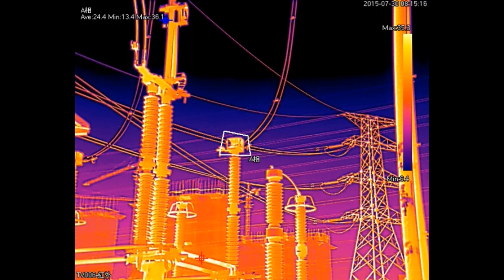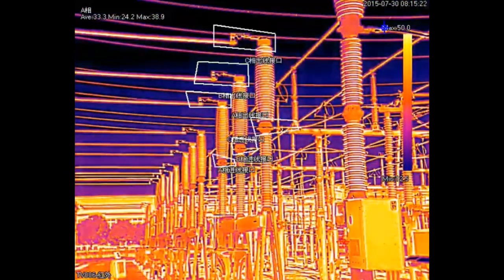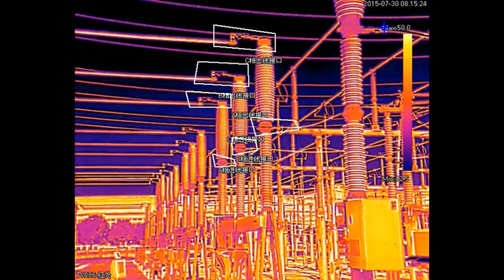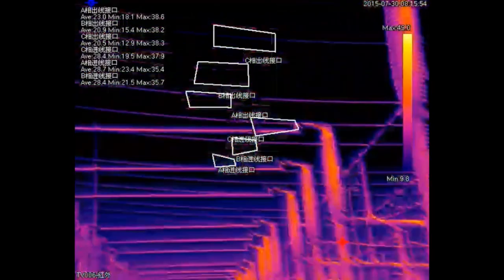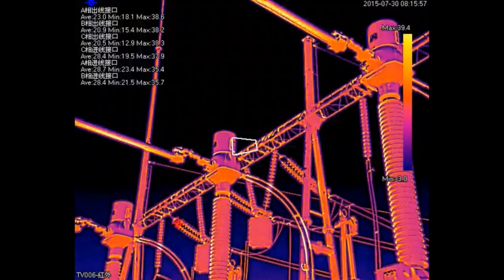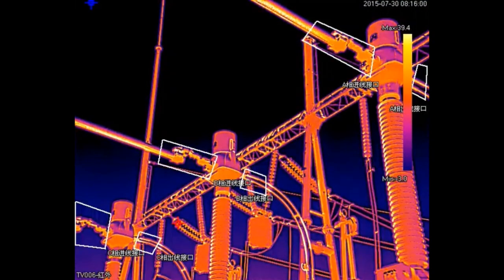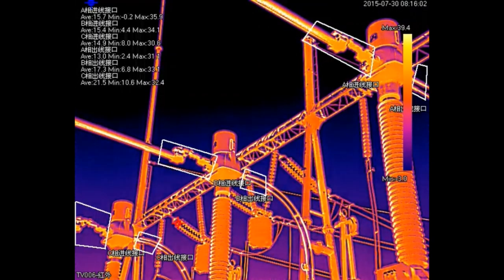This one is configuration, guys. Look at those hotspots. We've in fact targeted specific hotspots on specific presets. And then of course it's telling us the raw temperature of these electrical devices. In the event that one of them is outside of the temperature threshold, the alarm will fire. Look at that, that's brilliant. And then of course it will just go on all day doing that. Perfect.